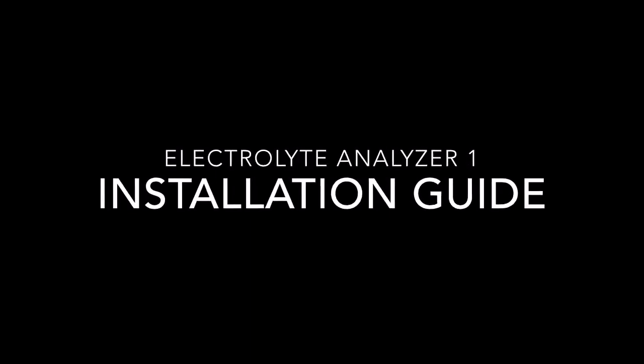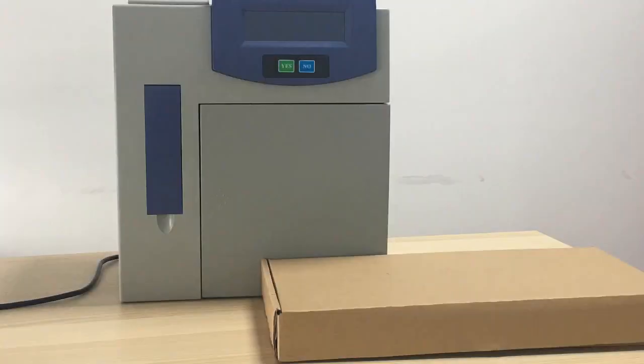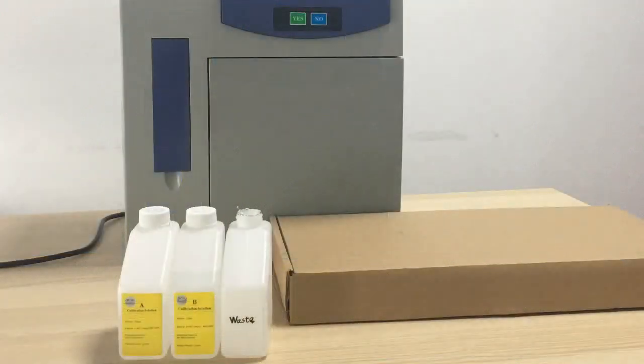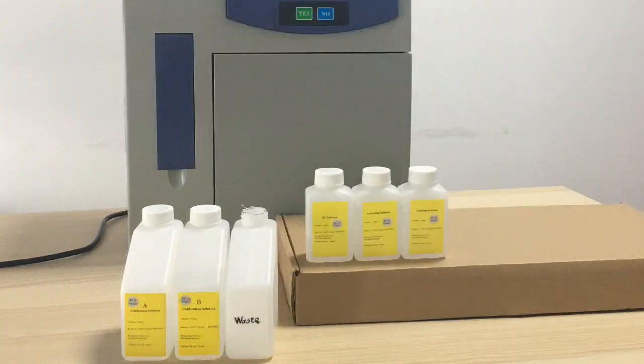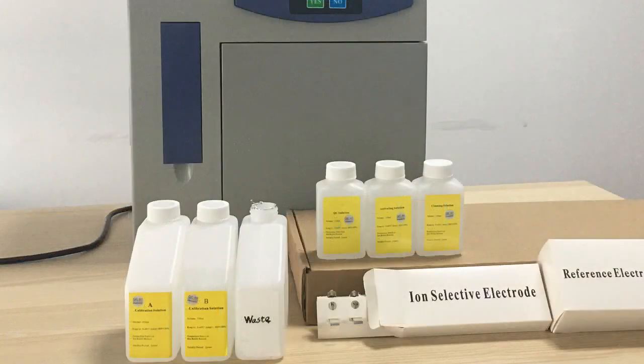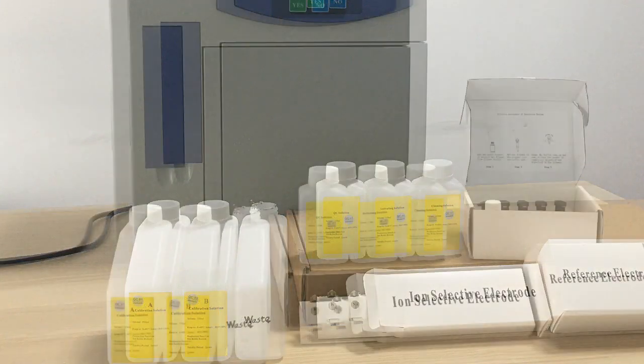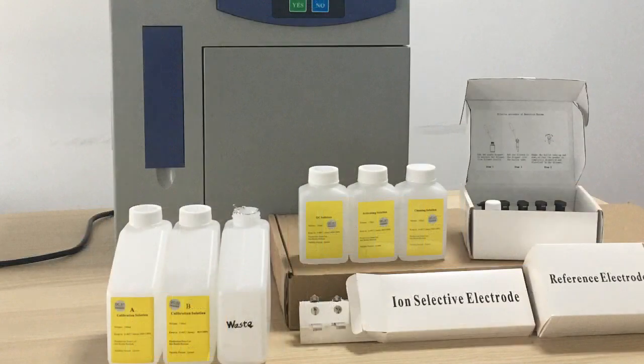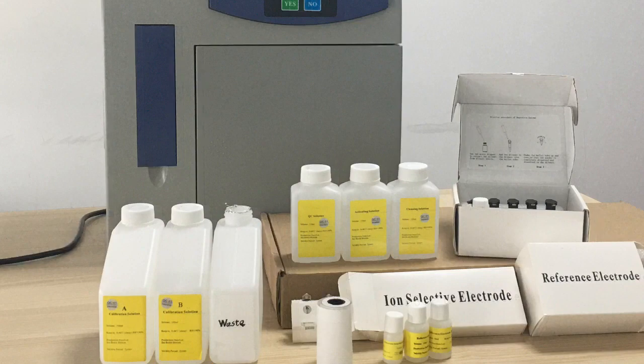Electrolyte Analyzer Installation Guide. First, we put the machine and the accessory box on the table. Then take out the reagent, calibration A and B, the QC solution, activating and cleaning solution, the electrodes, the cleaning set, and the internal electrode solution.